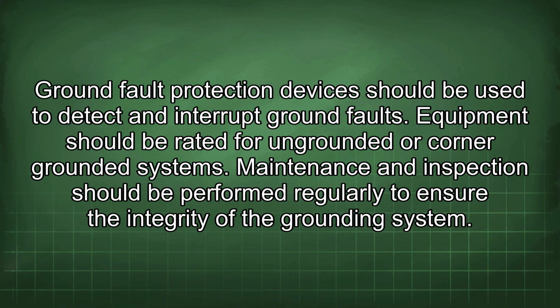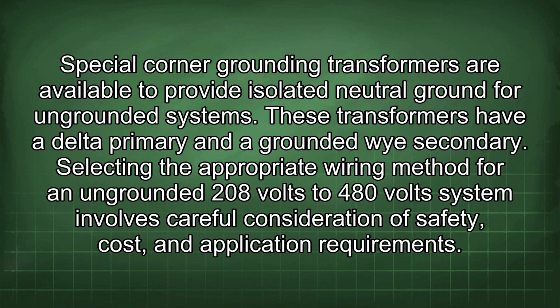Ground fault protection devices should be used to detect and interrupt ground faults. Equipment should be rated for ungrounded or corner grounded systems. Maintenance and inspection should be performed regularly to ensure the integrity of the grounding system. Special corner grounding transformers are available to provide isolated neutral ground for ungrounded systems. These transformers have a delta primary and a grounded Y secondary.